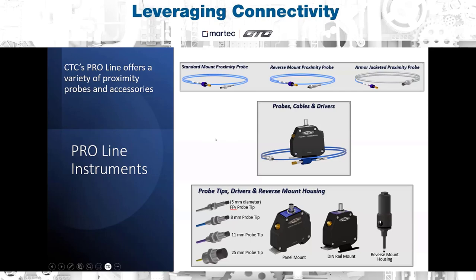Whenever you're getting a proximity probe system, it's best practice to get a separate probe and extension cable. This makes it easy to switch out components if they get damaged. It also makes them easier to stock. And then we offer 4 different types of proximity probes. They're delineated by the diameter of the probe tip, and the diameter of the probe tip directly correlates with the measurement range of each sensor.